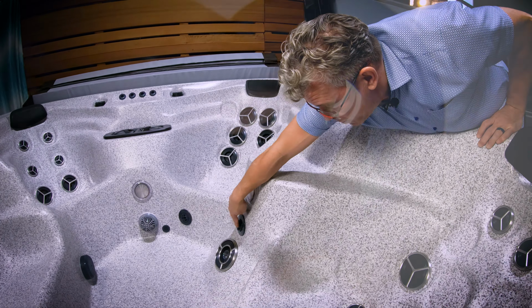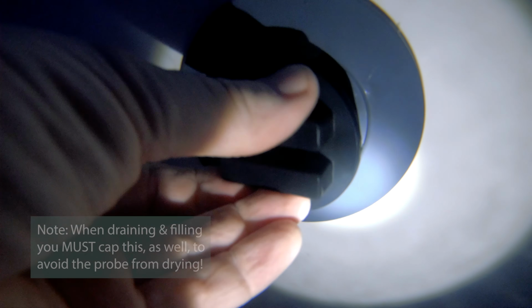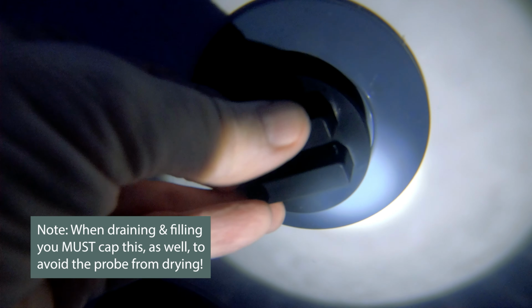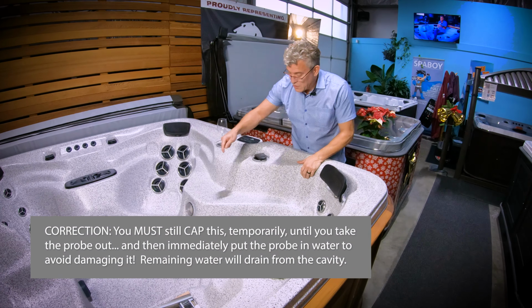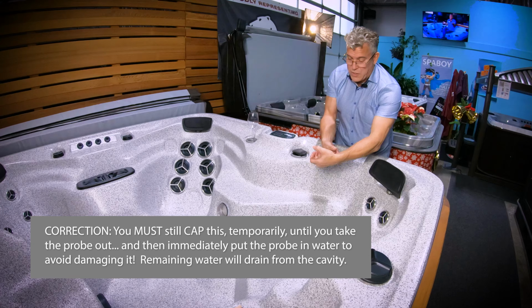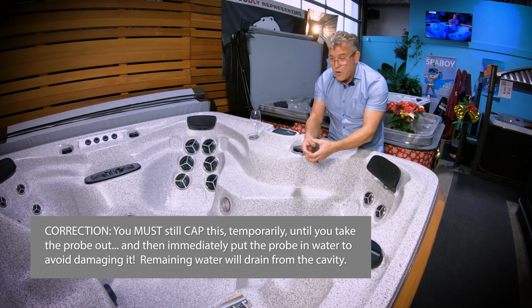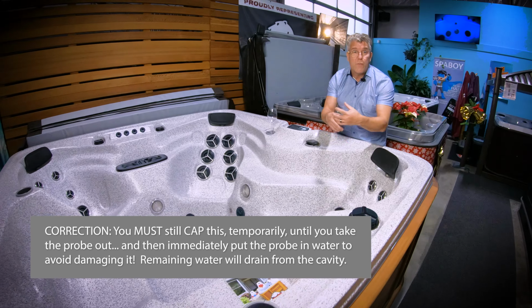Normally we plug this and drain because we're going to fill it right back up. But you can't do that if you're winterizing, because the water caught in there that keeps the probe wet will freeze and you'll break the fitting, the probe, everything.